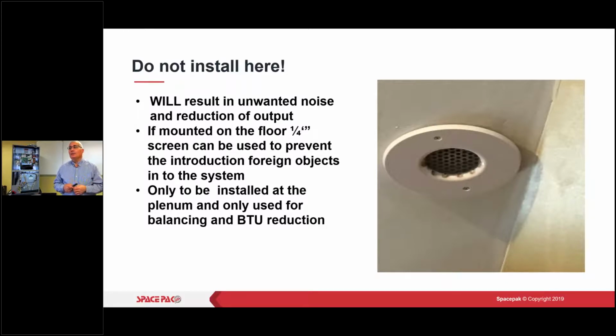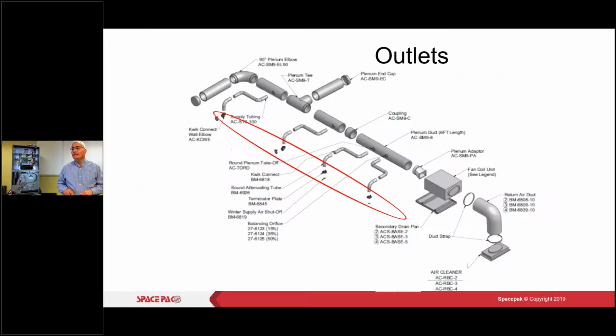So this is where you don't want to install them here. You want to install them, as it says right here, only at the plenum and only used for balancing or BTU reduction. You can use that as a screen, especially if it's a floor type of install, because you want to keep little Johnny from putting his marbles or whatever down into the tubing. Or little Anthony. Kid's a terror, all right?